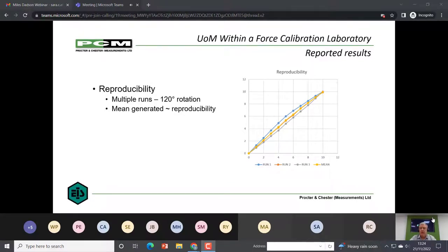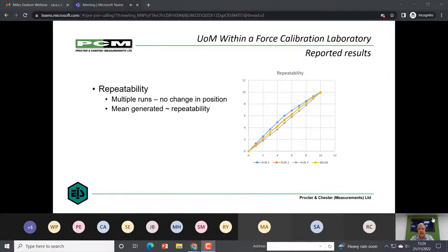Reproducibility is the part of the calibration where you rotate the device through 120 degrees into three independent setups. You carry out a mean of the three runs, and then you produce reproducibility as a function of the worst deviation from that mean. Repeatability is very similar. This time there is no change in position, and again a mean is generated and a repeatability worst case from the deviation from that mean.